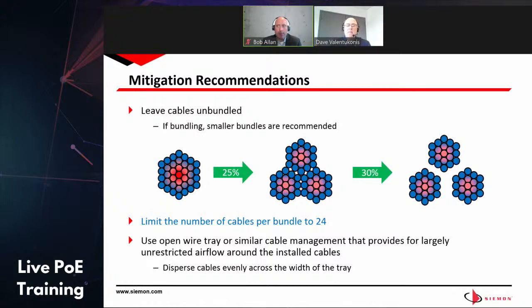So simply moving away from those big bundles to more managed bundles is a good thing. What we typically recommend is to limit those cable bundles to 24 as they come back in. Why? Because that aligns with your patch panel counts. It's an easy number to remember. And as you'll see on one of our cable dissipation tables, it matches the allowable cable bundle sizes you can do with category 6A shielded cabling.